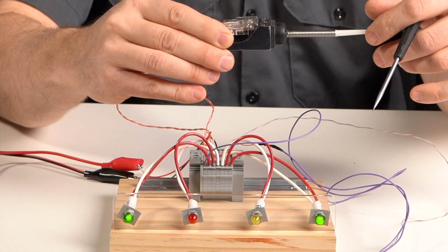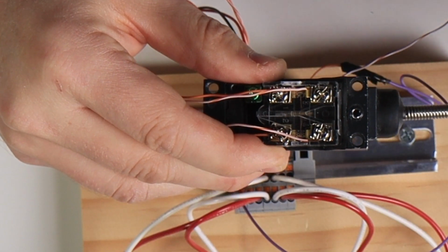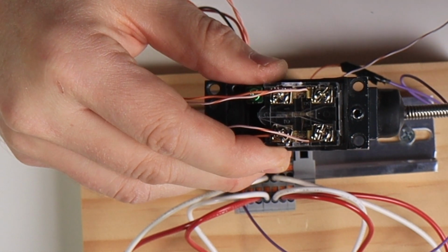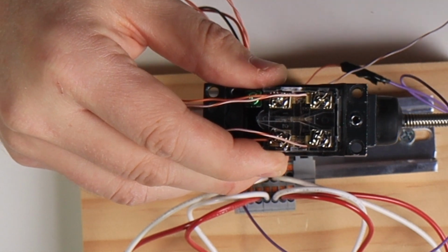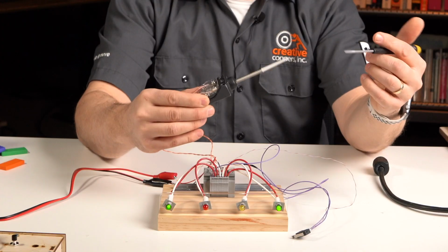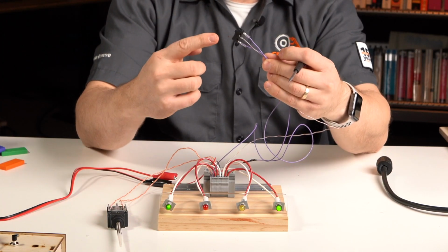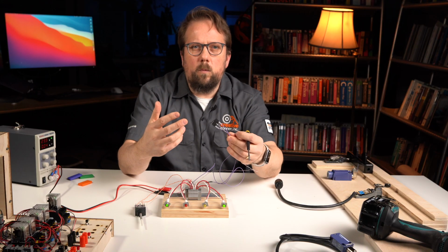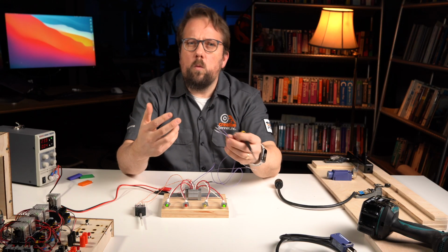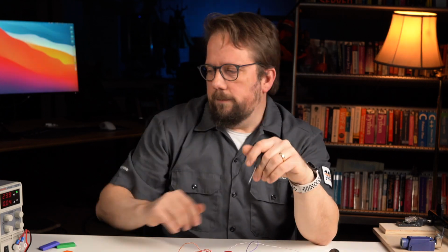As I press the actuator, you can see the copper bars that span across the terminals moving. One moves to open the circuit and the other moves to close the circuit. Even though this one is double pole and this one is single pole, either one can be wired either as normally open or normally closed. So which way should we wire them up? Normally closed. Let's look at why.